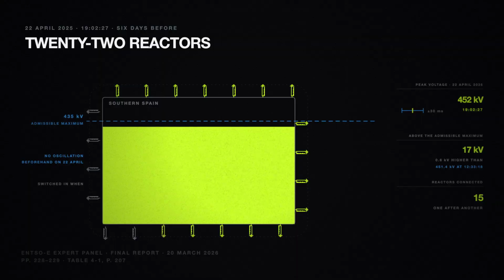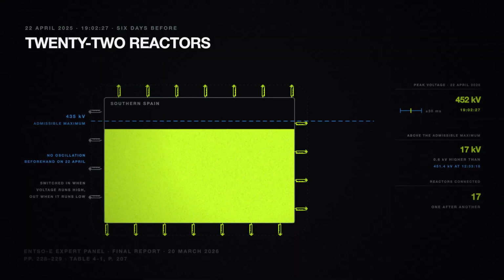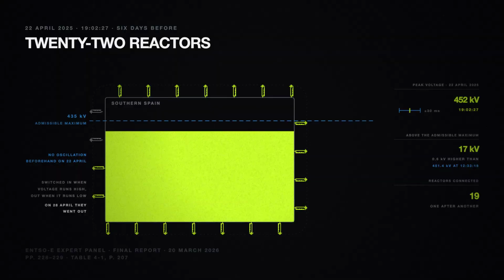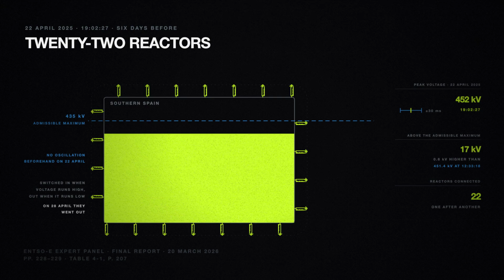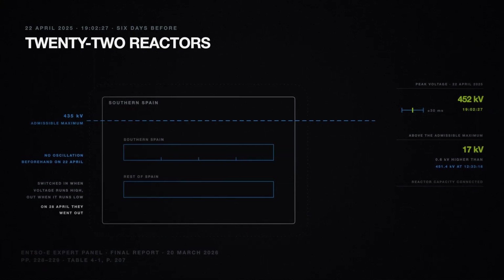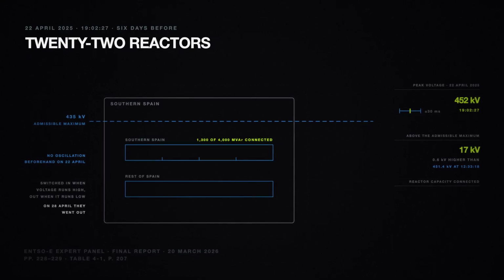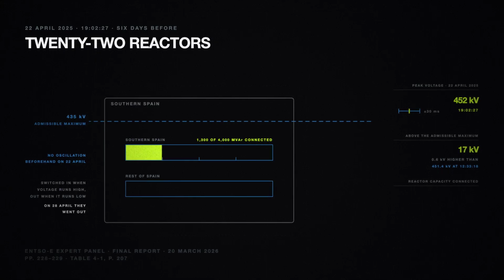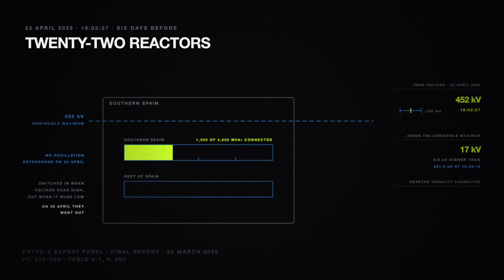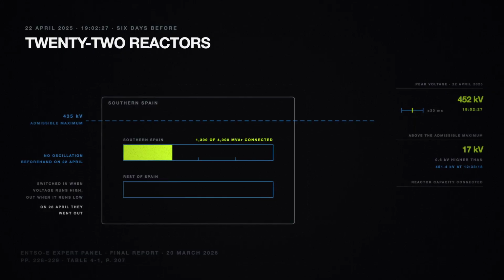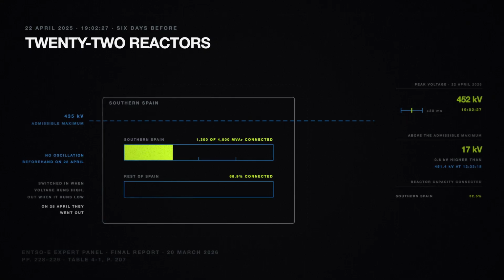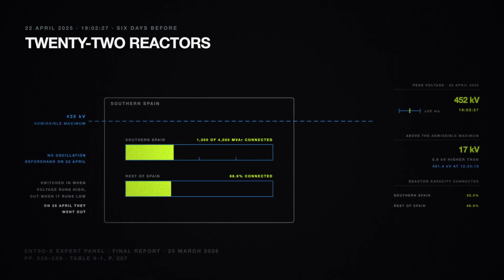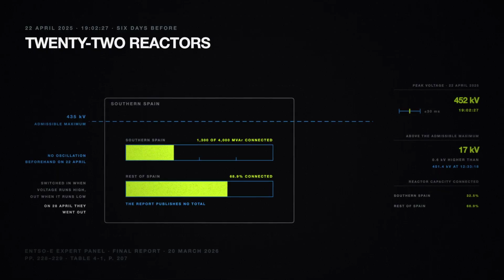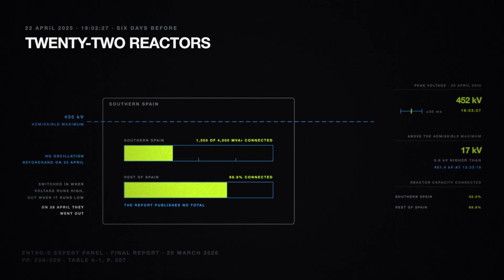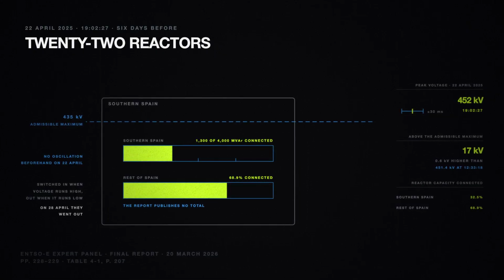Reactors are switched in when voltage runs high and out when it runs low. That is how they were used on both evenings. Through the oscillation episodes on the 28th, voltage had been going low and reactors had been switched out. By the time the system went dark, southern Spain had 1,300 megavolt amperes reactive of reactor capacity connected out of 4,000, 32.5%. In the rest of Spain, 68.9% of what total, the report does not say. It gives that share and no megavolt amperes to go with it.